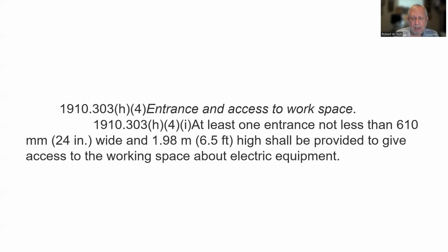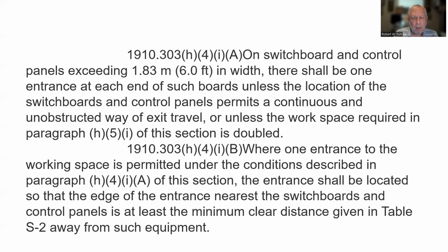Entrance and access to workspace. At least one entrance, not less than 24 inches wide and 6.5 feet high, shall be provided to give access to the working space about electric equipment. On switchboard and control panels exceeding 6 feet in width, there shall be one entrance at each end of the boards unless the location of the switchboards and control panels permits a continuous and unobstructed exit way of travel, or unless the workspace required in paragraph H5I of this section is doubled. Where one entrance to the working space is permitted under the conditions described above, the entrance shall be located so that the edge of the entrance nearest the switchboards and control panels is at least the minimum clear distance given in table S2 away from such equipment.